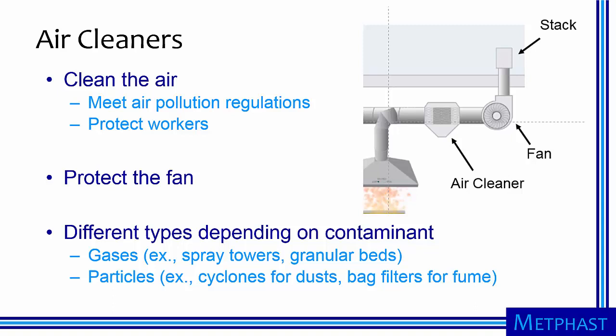Air cleaners serve, obviously, to clean the air. How well they clean the air depends on the purpose. If the air is being exhausted outside, they need to be designed to meet air pollution regulations. Alternatively, they need to be effective enough to protect workers if the air is recirculated back into the facility. Air cleaners also serve to protect the fan, as some gases are highly corrosive and some particles can erode the fan blades. There are many different types of air cleaners depending on the contaminant being cleaned. Spray towers and granular beds are used to absorb gases. Cyclones and bag filters are common air cleaners for particles.